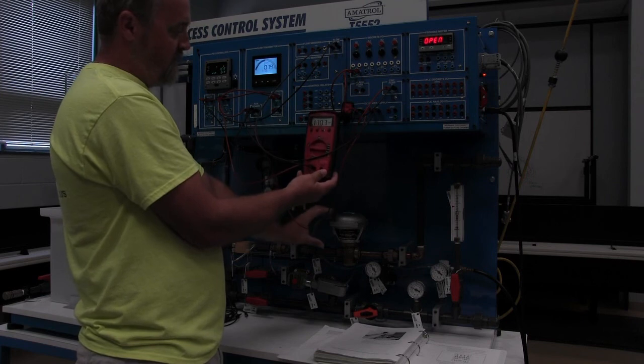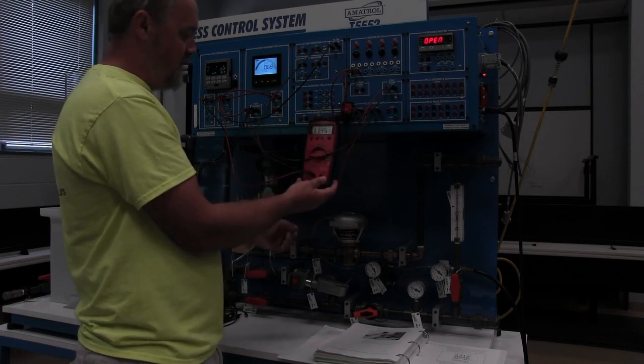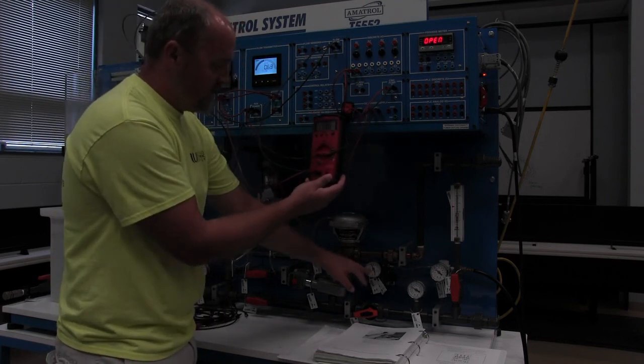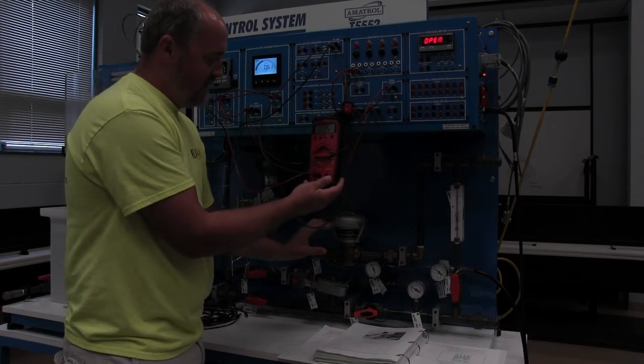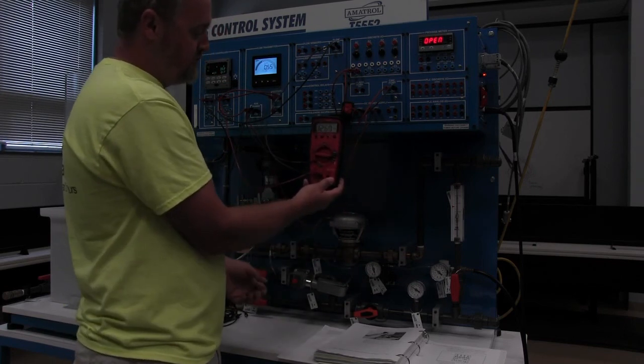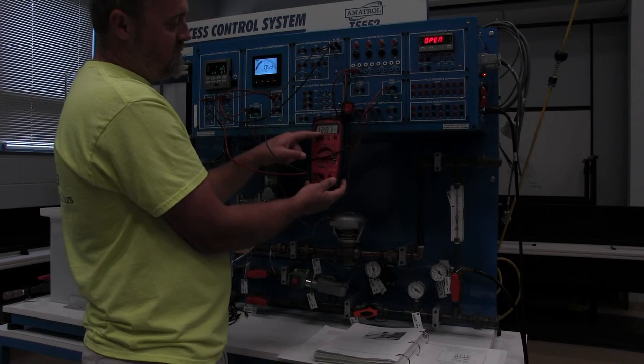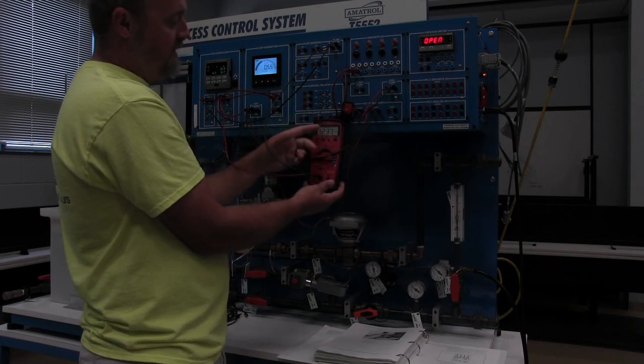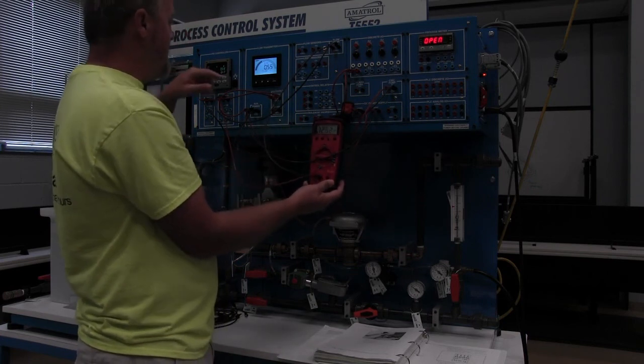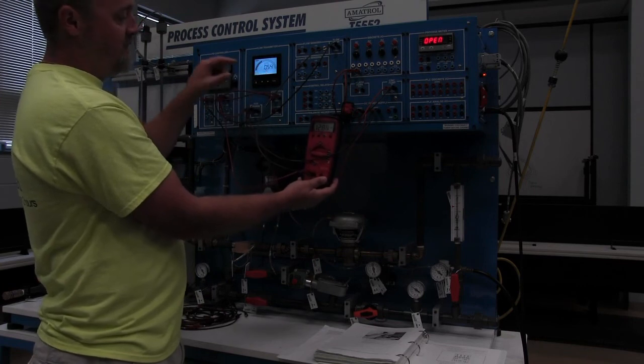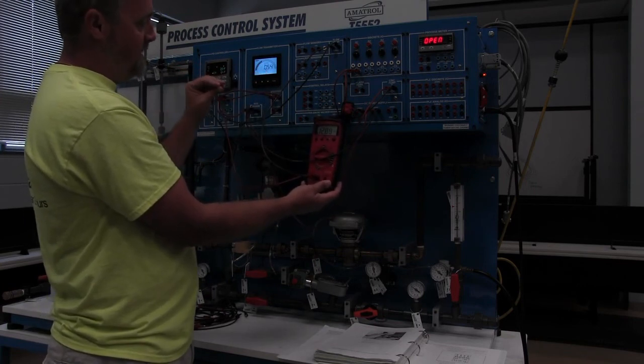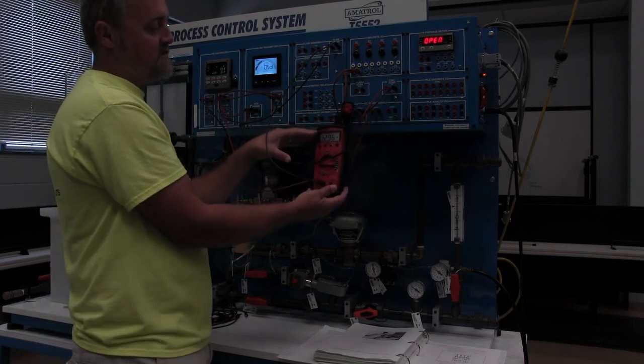So in order to slow this down, this valve has to close. And in order for this valve to close, the milliamp signal has to go up to this IP converter to allow this valve to open and close properly. So you can see my milliamp signal is increasing. It increased to a 12.8.